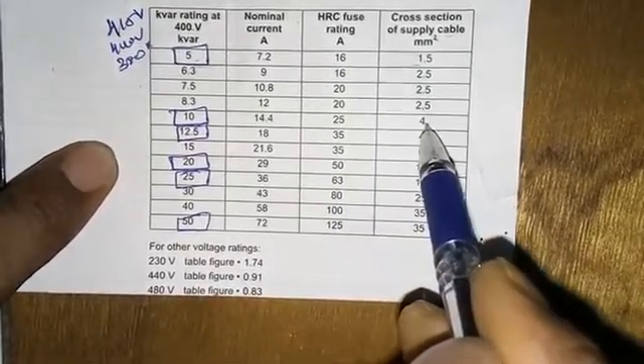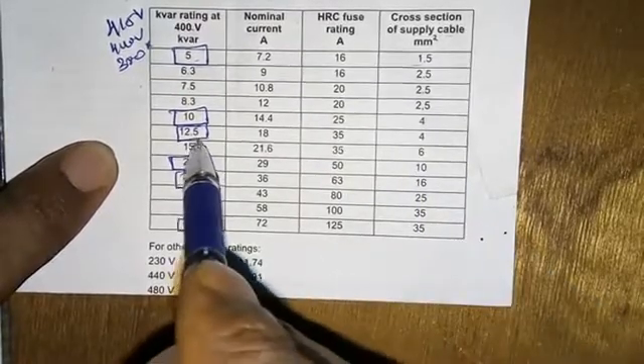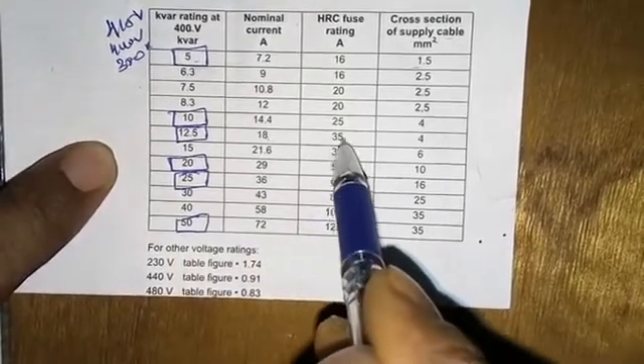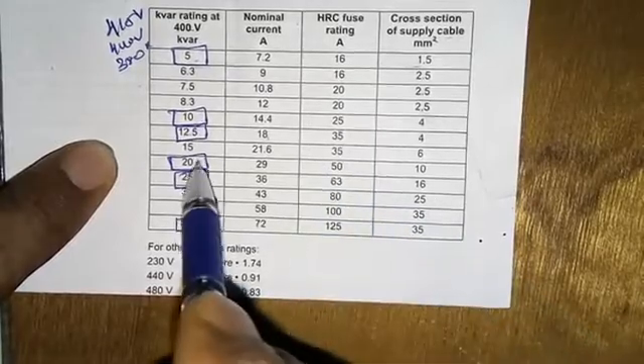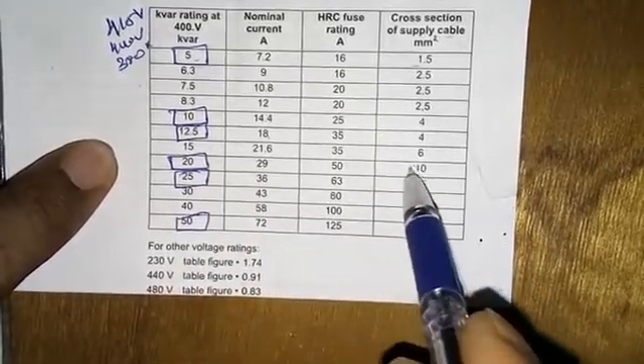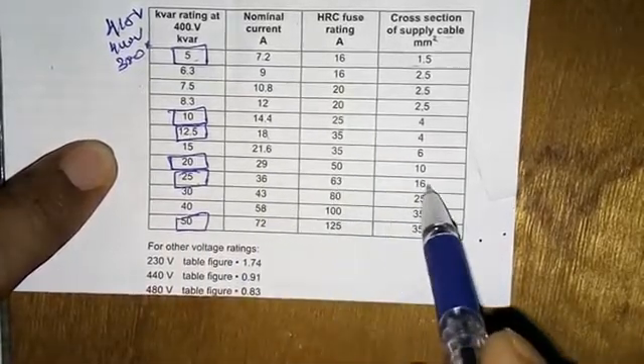This is the standard. For 12.5 kVAR, it's 18 ampere current consumption with 35 ampere HRC fuse and 4 square mm cable. For 20 kVAR, it's 29 ampere with 50 ampere HRC fuse and 10 square mm cable.